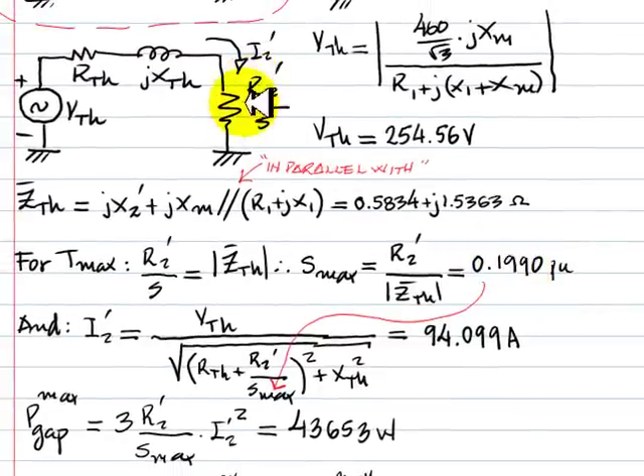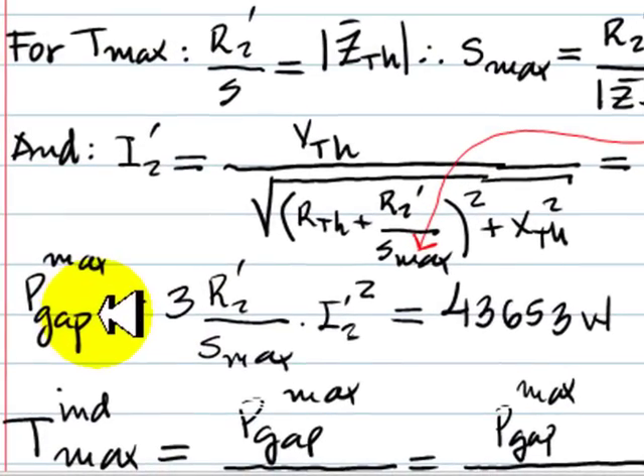To find the maximum torque, we compute the gap power — the power in this resistor — then multiply by 3. We compute this current as VTh divided by the total impedance magnitude: the Thevenin impedance in series with R2' over Smax. Taking the absolute value — squaring the real part, squaring the imaginary part, taking the square root — that current is 94.1 A. We square that current, multiply by this resistance at S equal to Smax, multiply the whole thing by 3, and we have the gap power for maximum torque: 43.7 kW.